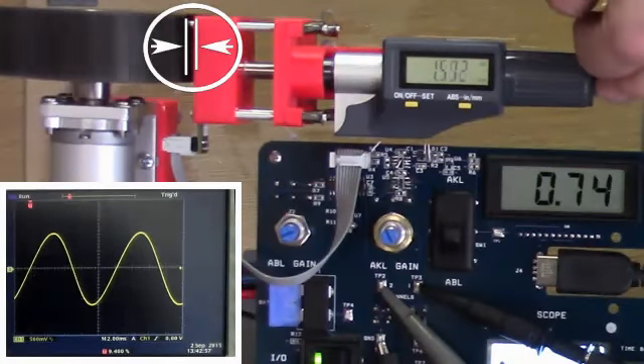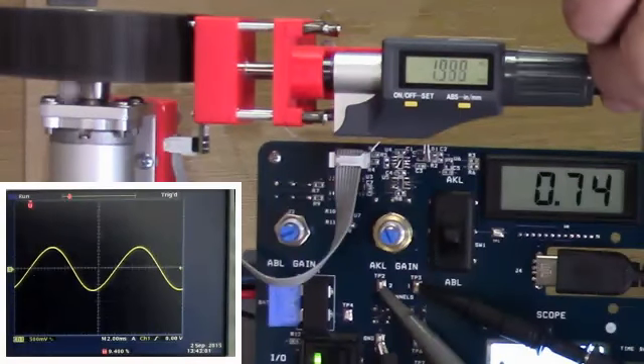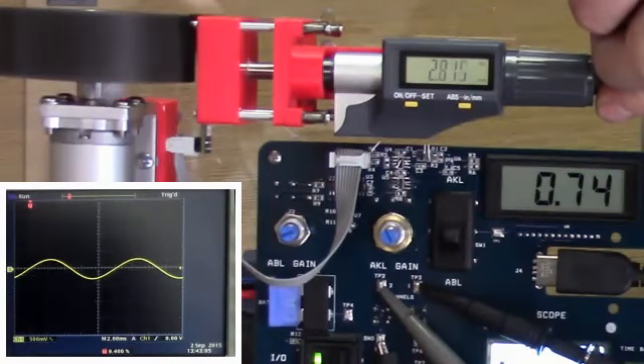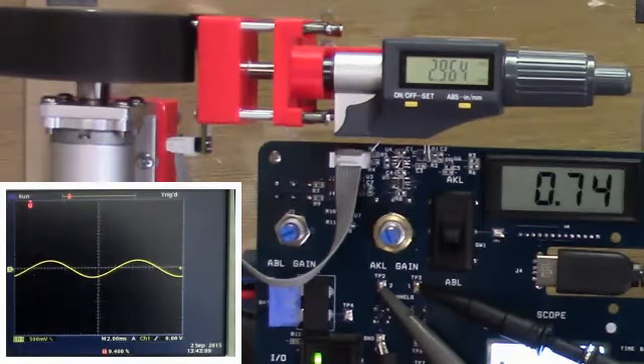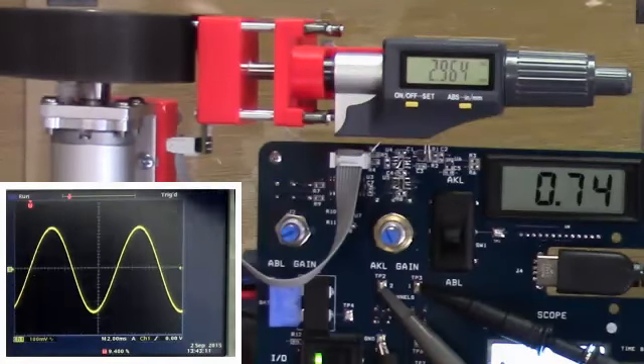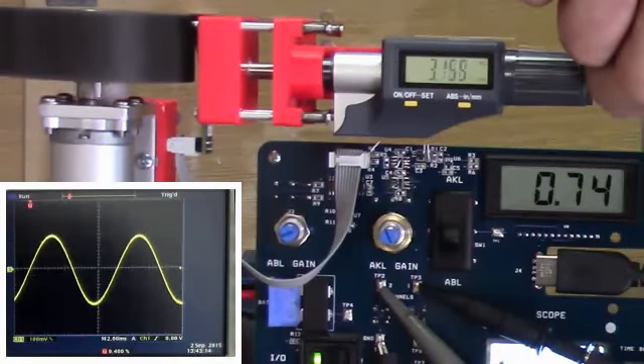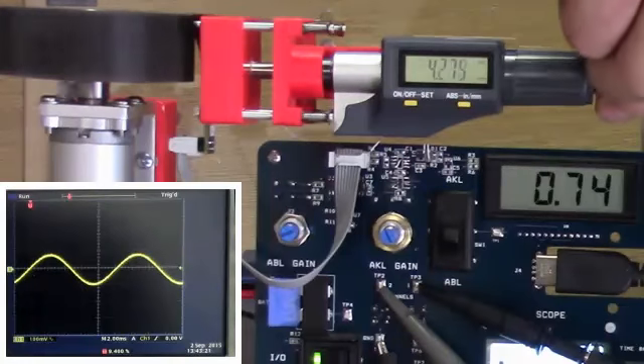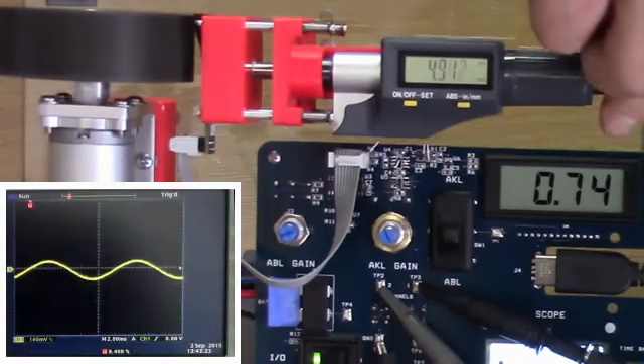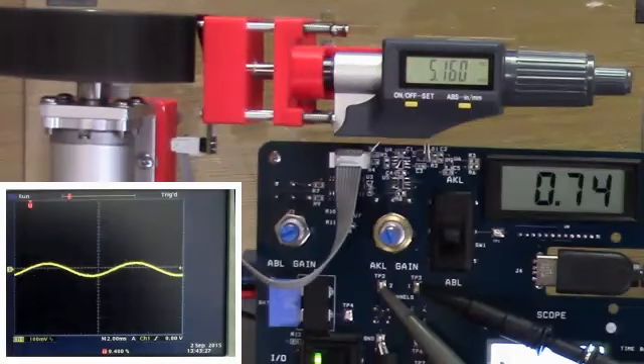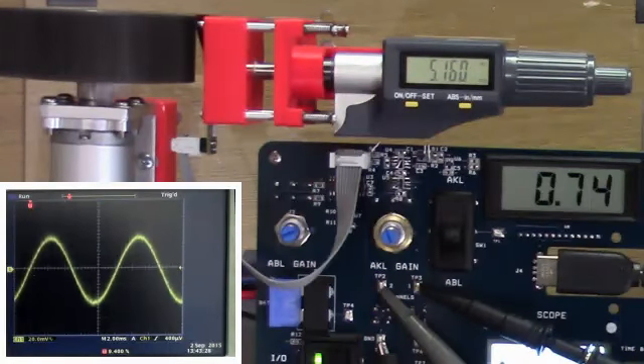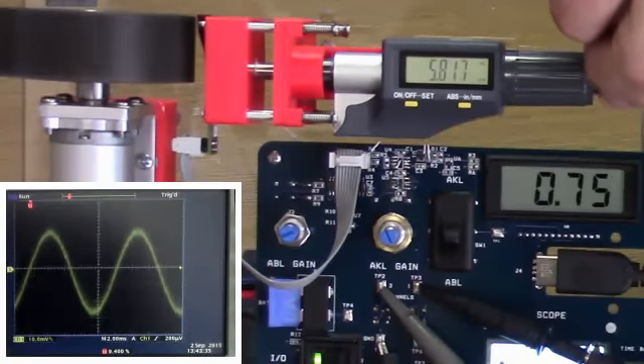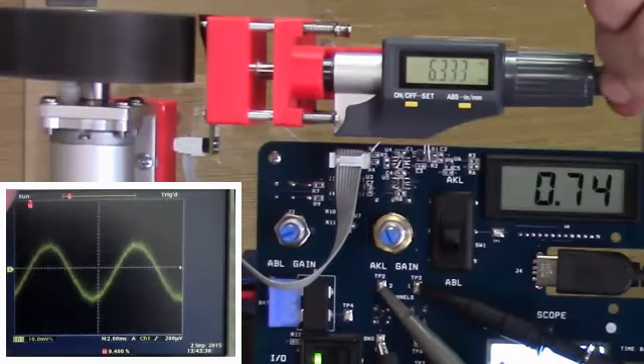As I increase the air gap you can see the output amplitude decreases but stays a symmetrical sine wave. The amplifier has a gain of about 20 so the amplitude even at the large distances is several millivolts. With a large gear like this the sensors typically operate over at least a five millimeter air gap range.